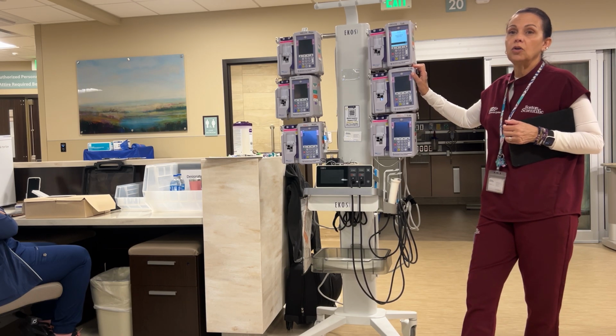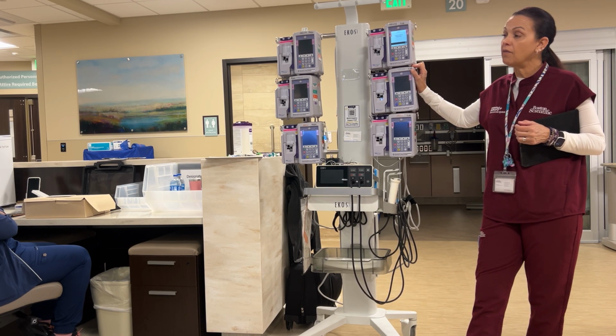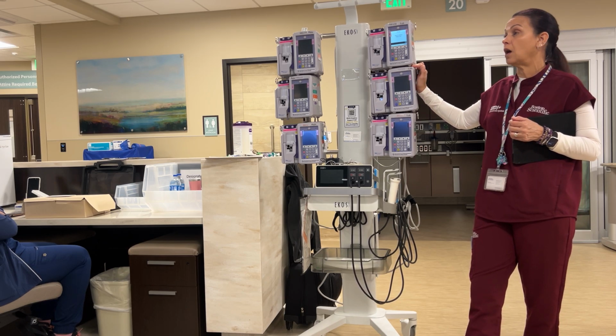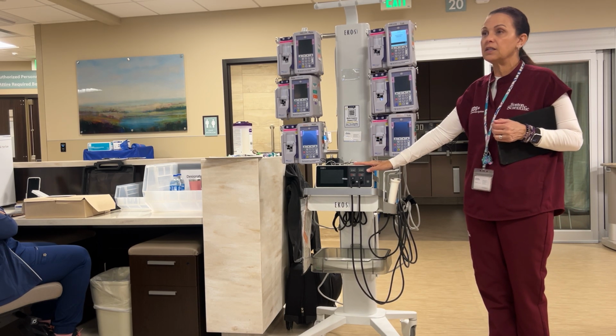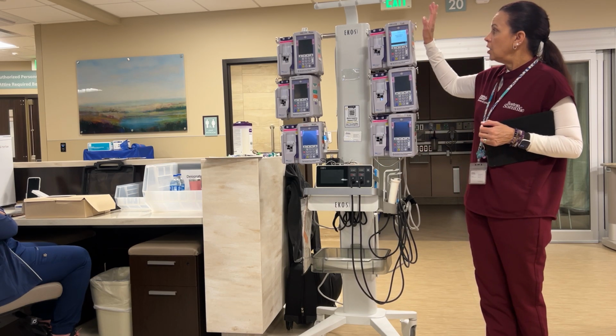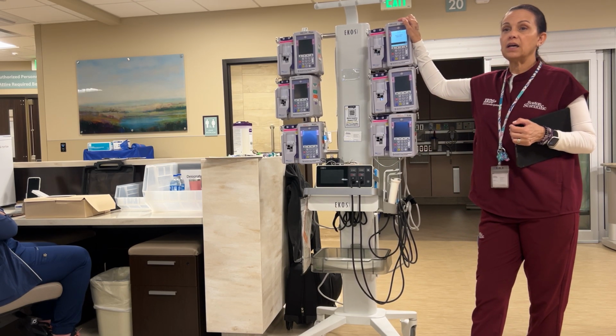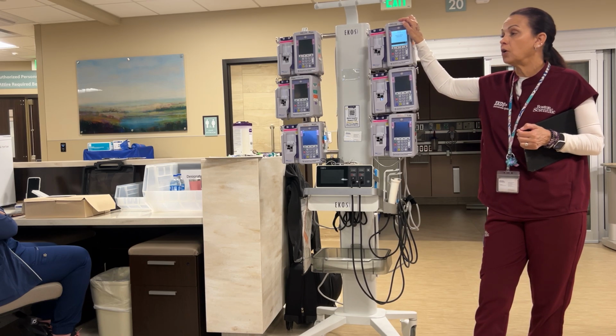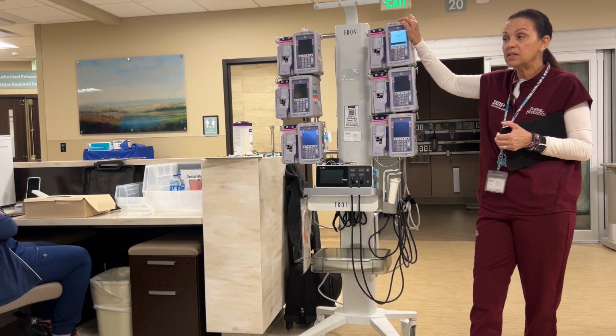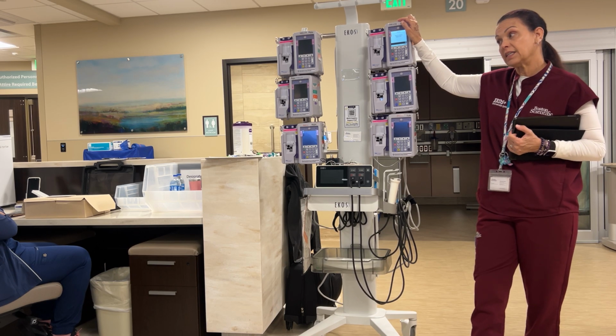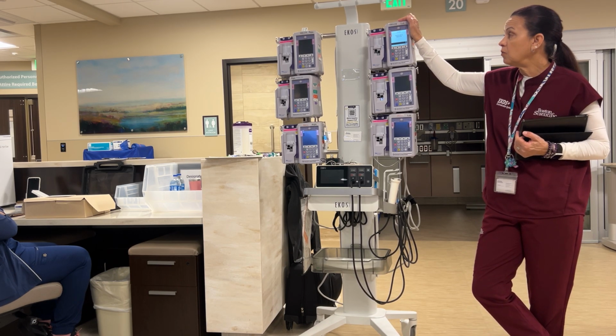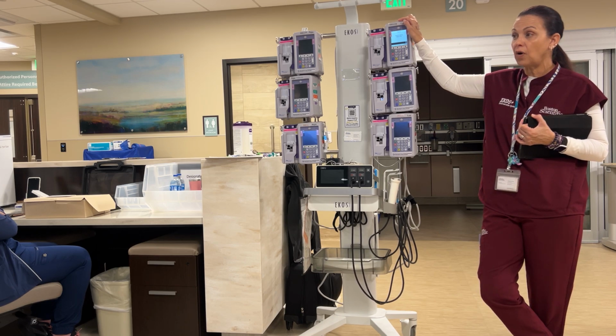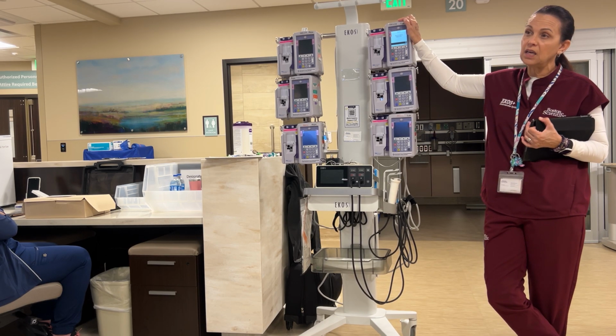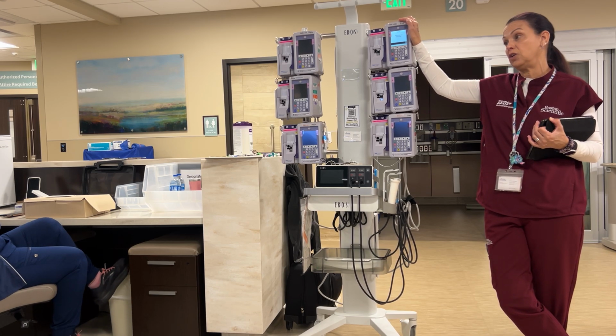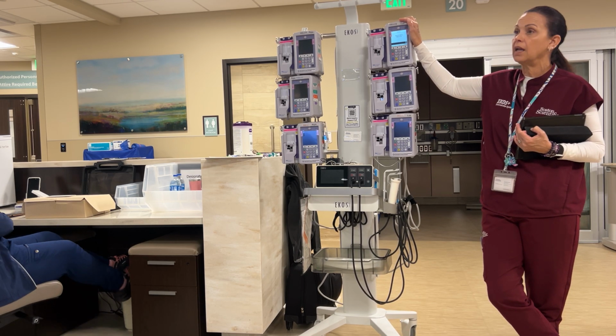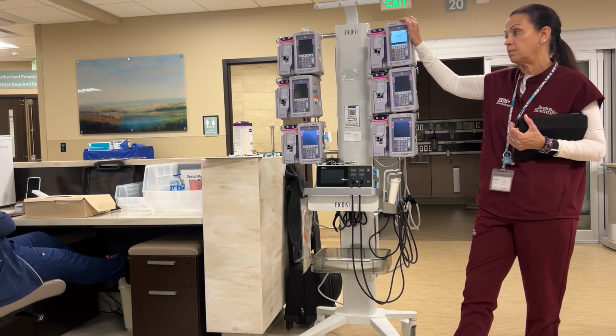Your coolant, normal saline, is going to run at a minimum of 35 ml per hour, and can be titrated up to 120 ml if we get a temperature error on the control unit. Sheath management, that is normally a subtherapeutic dose of heparin. It is determined by the physician on a per patient basis. We at Boston Scientific do not dictate that dose. It can be referenced from any of our trials, but most of the time we see anywhere from 300 to 500 units per sheath. And again, that is determined by the physician on a per patient basis.